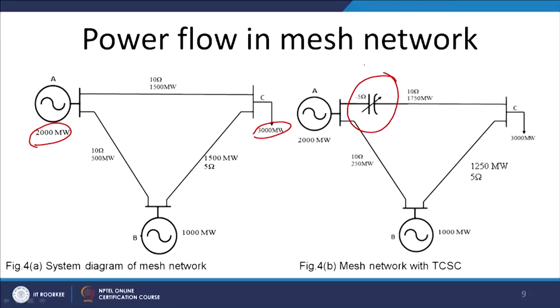So we can reduce the power flow through the line AB by having a solution given by FACTS. We can insert a variable series impedance to reduce the impedance of the line, thus enhancing the power carrying capability of the existing line, and it reaches another 250 megawatt of power. Thus only 250 megawatt of power is wheeled through the line AB, and thus it reaches through C. So the wheeled power cost decreases in this case while using FACTS devices.